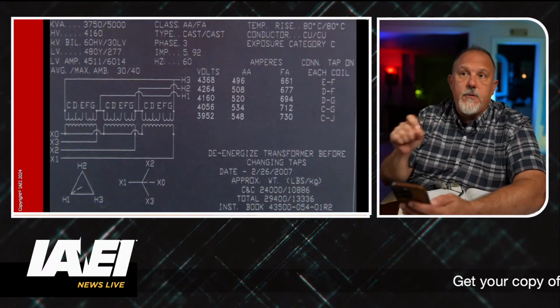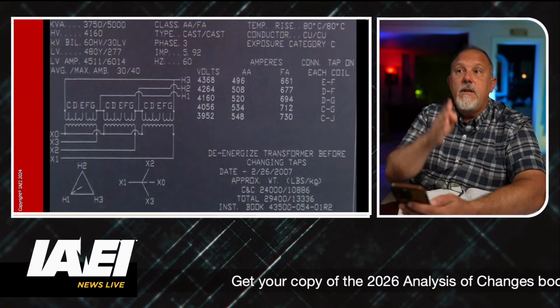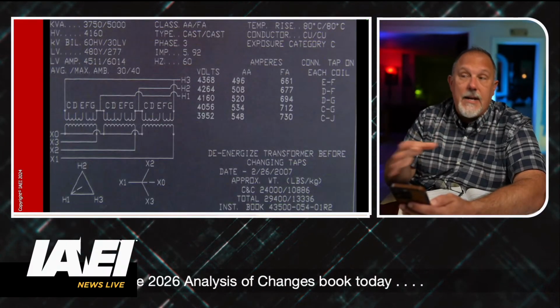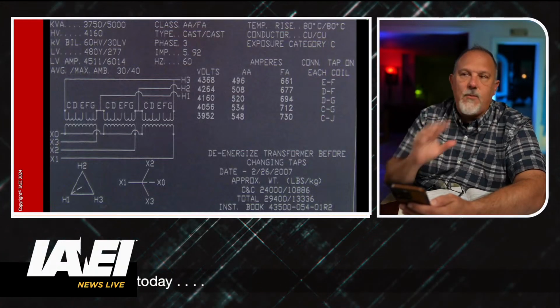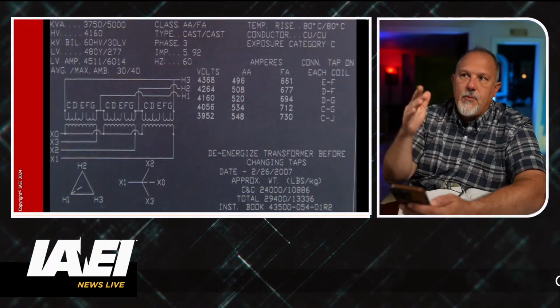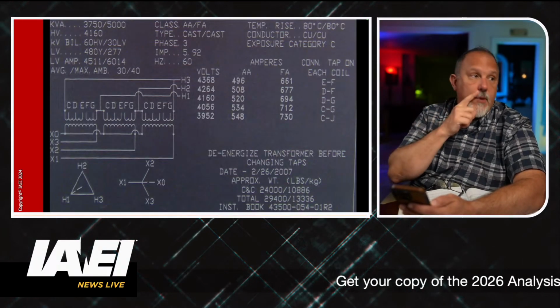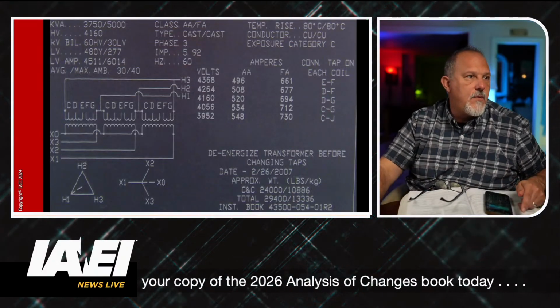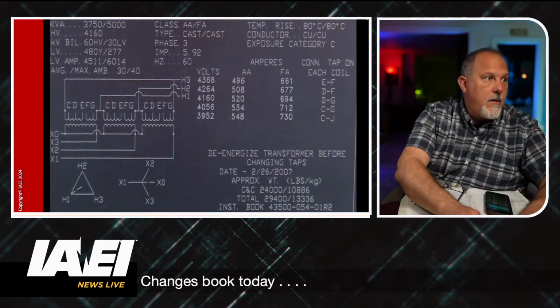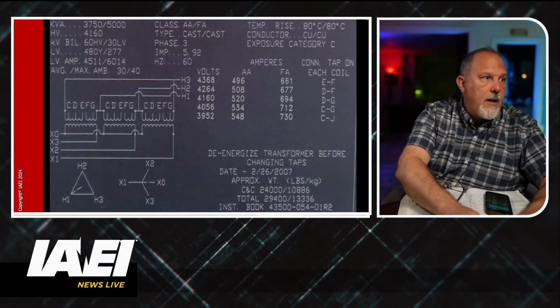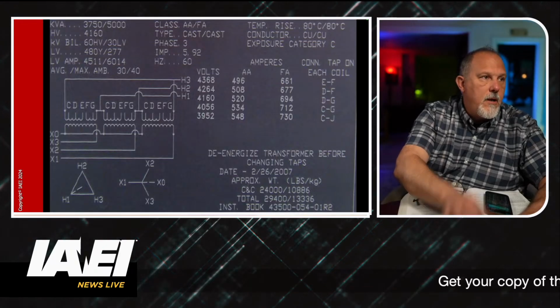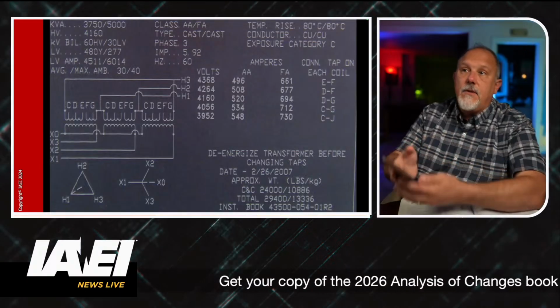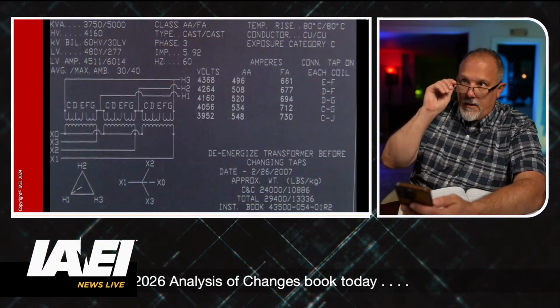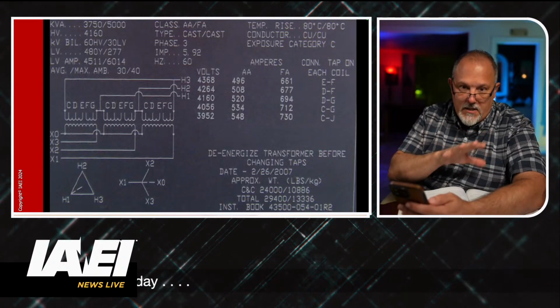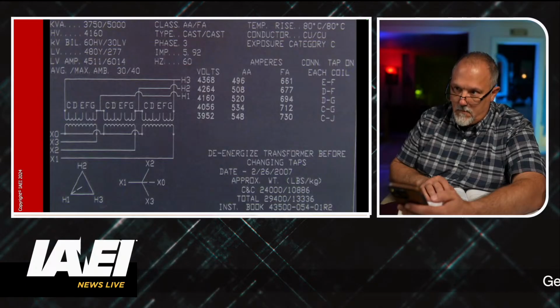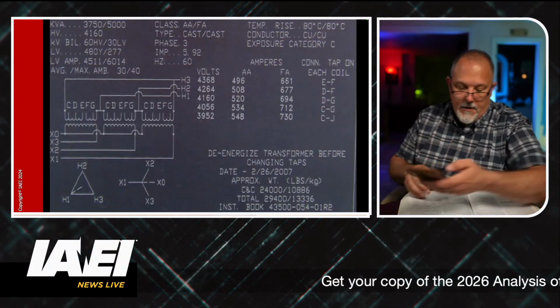I'm going to do the available fault current, which will be based upon the base kVA divided by the base impedance, 5.92, and I could lower that. I could do my 80%. I can lower my 5.92 because of the error margins, and I've got to look up what the error margin for impedance is on a medium voltage transformer. I know we typically use plus or minus 10%. It may be different for a medium voltage transformer. I just want to confirm that. But that would give me my maximum, and that would be based upon the full load amps of the 3750.